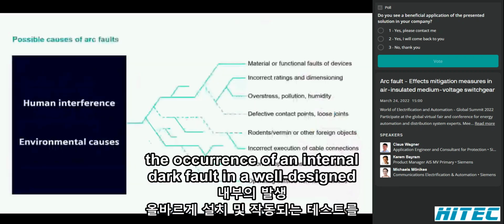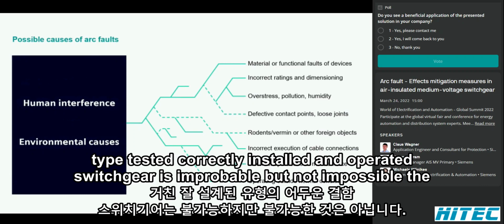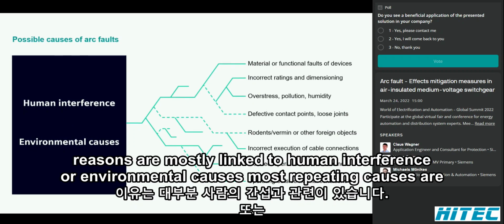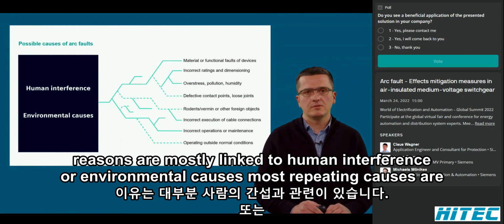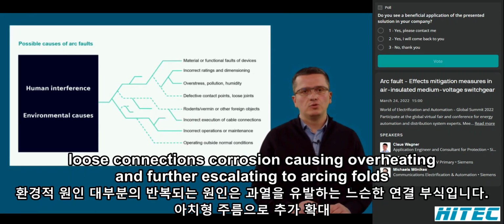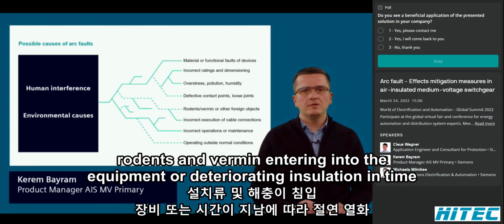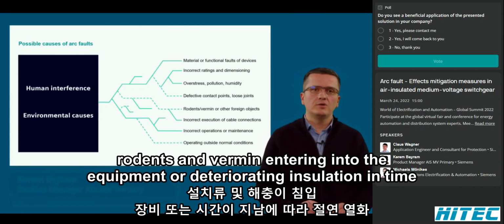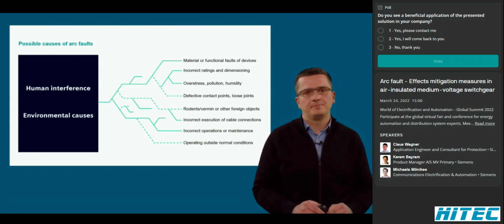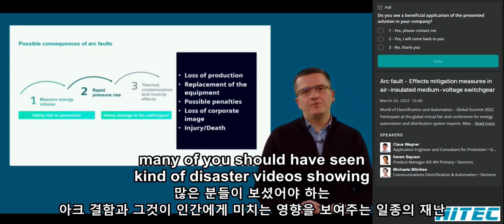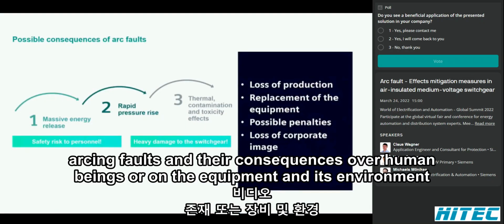The occurrence of an internal arc fault in a well-designed, type-tested, correctly installed, and operated switchgear is improbable, but not impossible. The reasons are mostly linked to human interference or environmental causes. Most repeating causes are loose connections, corrosion causing overheating and further escalating to arcing faults, rodents and vermin entering into the equipment, or deteriorating insulation in time. Many of you should have seen kind of disaster videos showing arcing faults and their consequences over human beings or on the equipment and its environment.